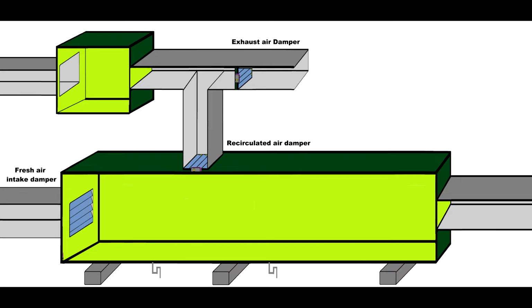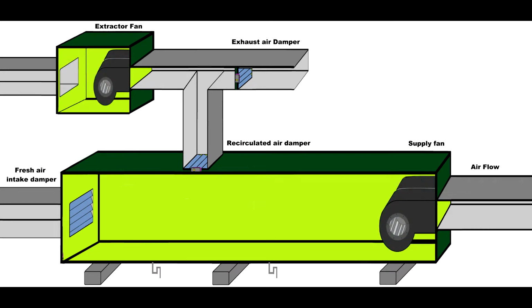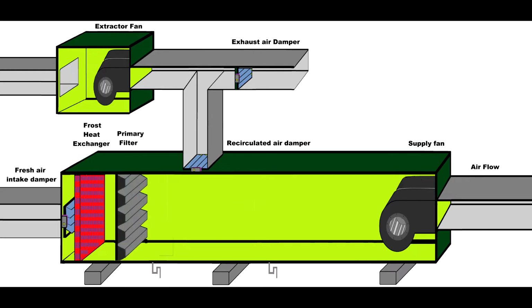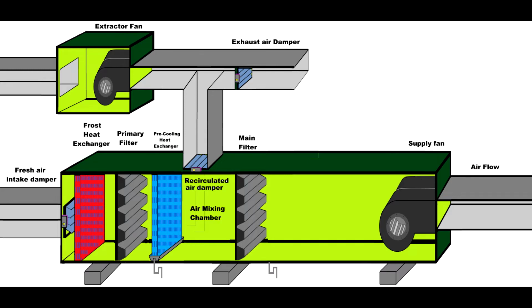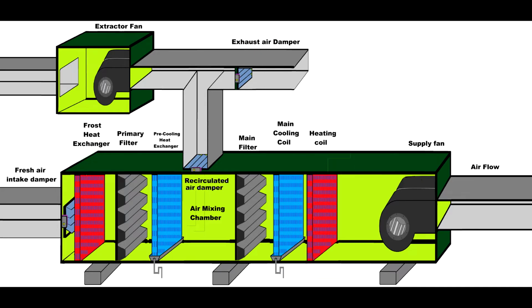Now, coming back to our AHU. An AHU needs dampers, and to circulate the air we need fans. But then we have to control the air temperature. The fresh air intake is controlled by a frost heat exchanger. The air has to be filtered by a primary filter, and then we have to remove the humidity by using a primary cooling coil. Then we have the main filter, because the return air must be filtered as well. And a main cooling coil, because we want to trim the air temperature. And the heating coil, to heat or reheat the air as needed. And a humidifier, in case we remove too much moisture while we're cooling the system.